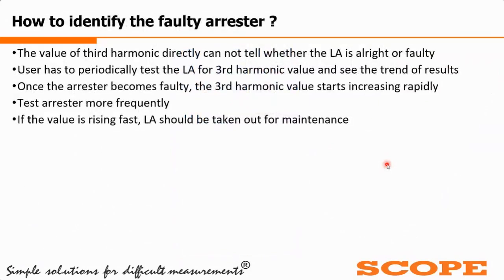That can be done. Now, coming to the very fag end of the session, how to identify the faulty arrestor. As I have told you earlier, the trend has to be noticed. If the third harmonic current value of the arrestor from day one of the LA is, let's say, 80 microamps or 90 microamps, you are happy. You keep on checking whether it is changing or not. But the moment it starts changing, you have to be more cautious, because when it starts deteriorating, it deteriorates very fast. So you have to be more vigilant when the result is showing an increasing nature, because a single value may not be the determinant for your LA health. So you have to see it as a trend.